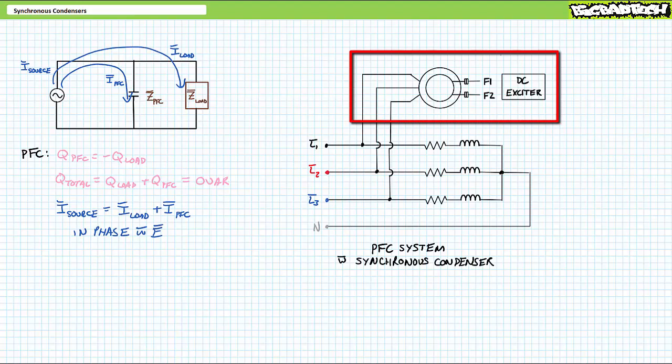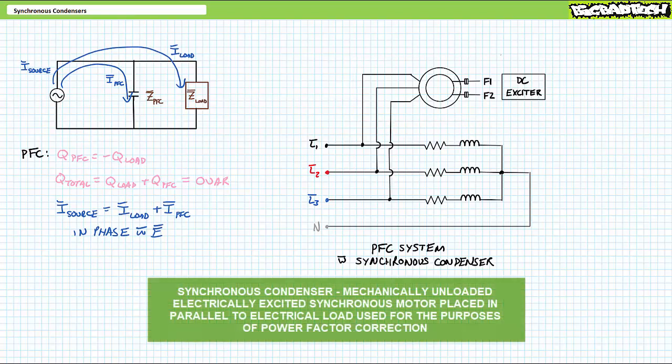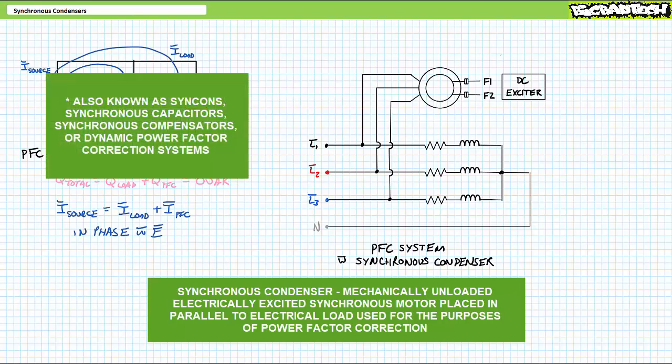A far more accurate and responsive method of live power factor correcting an electrical load is with a synchronous condenser, the topic of today's discussion. A synchronous condenser is a mechanically unloaded three-phase AC electrically excited synchronous motor placed in parallel to the three-phase AC network that requires power factor correction. By varying the field current to the free-spinning synchronous motor, one can find a sweet spot where the reactive power of the synchronous condenser is equal in magnitude yet of opposite polarity as the reactive power needs of the load.